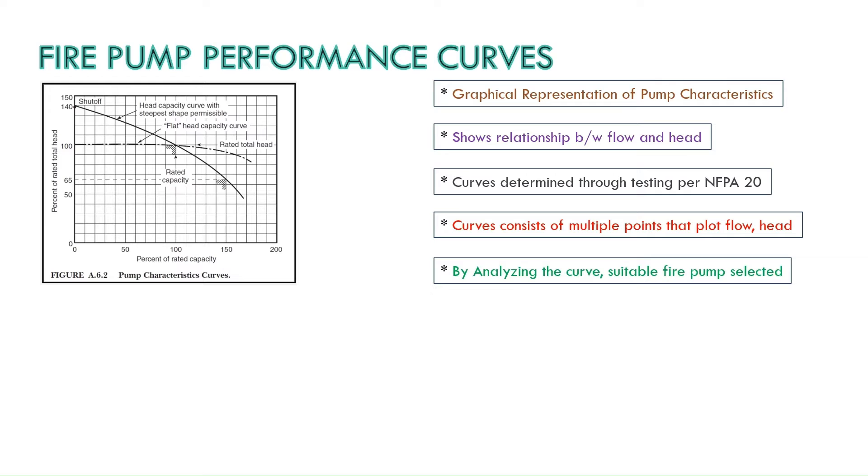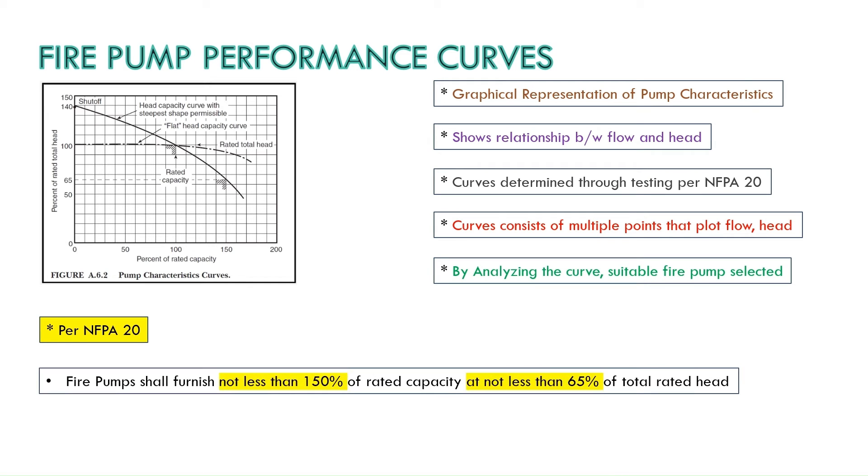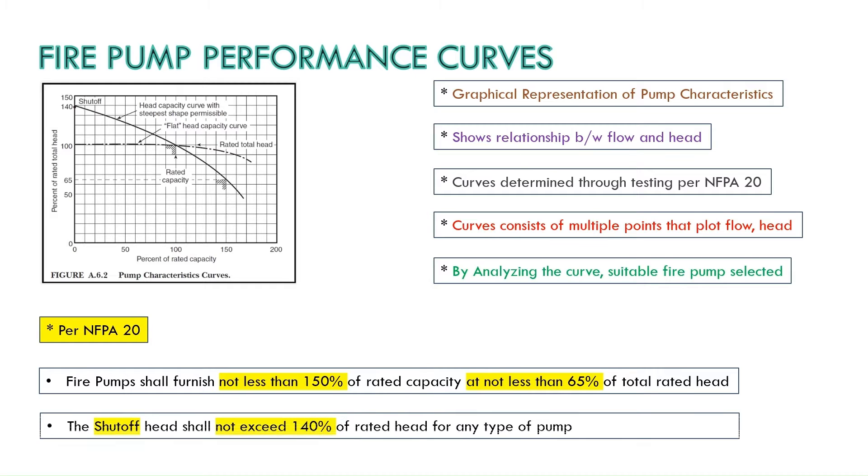Apart from this there are two most important points which are stated in NFPA 20. You need to make sure you are able to remember these two particular points since these are the deciding factors to select a fire pump. The first most important point is that the fire pumps shall furnish not less than 150% of rated capacity at not less than 65% of total rated head. And the second point is the shutoff head shall not exceed 140% of rated head for any type of pump.